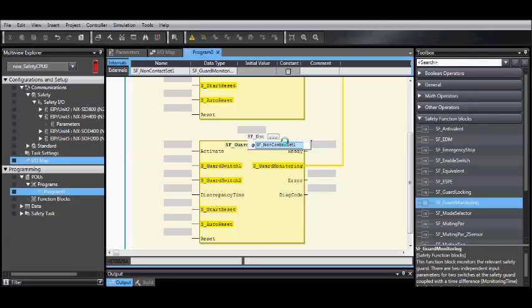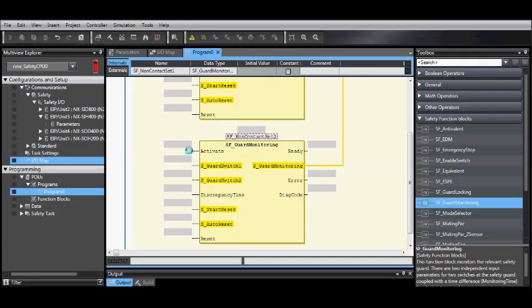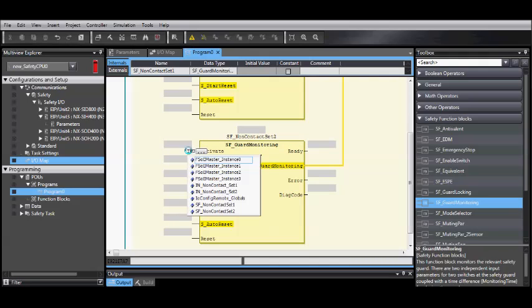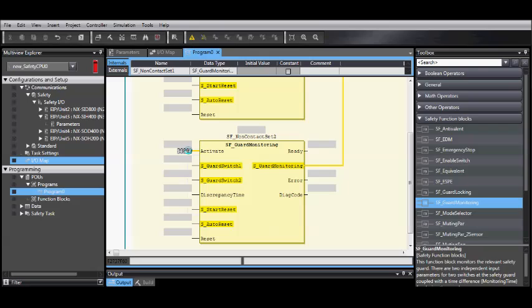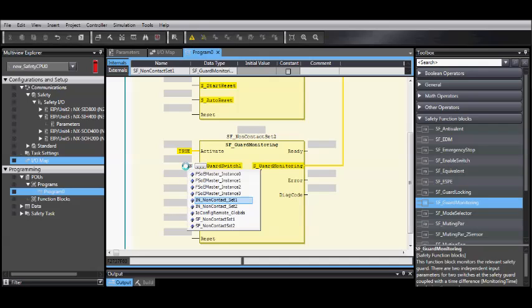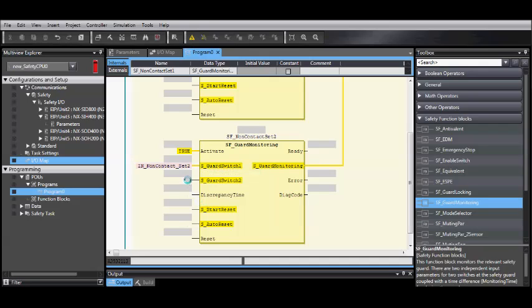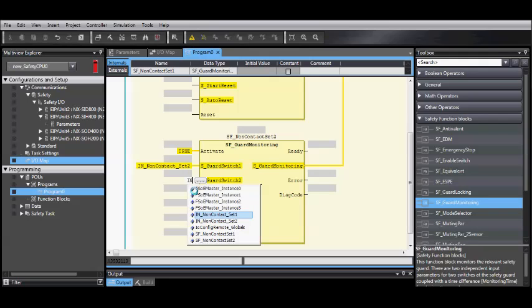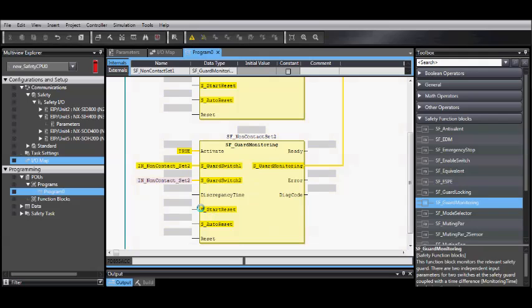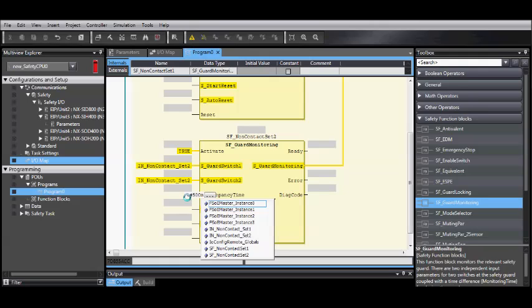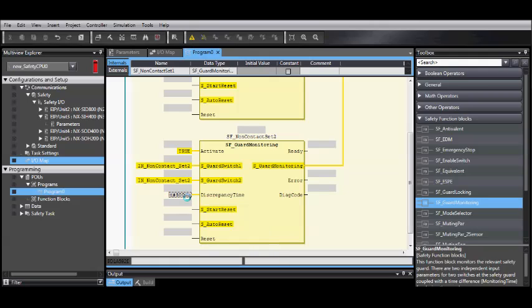Once again, give your new function block a unique name. For Activate, if you are not using the Safety Connection status, just enter TRUE. Now, select the non-contact switch for set 2 for both of the inputs. Discrepancy time is the same, T, pound, 500 milliseconds.